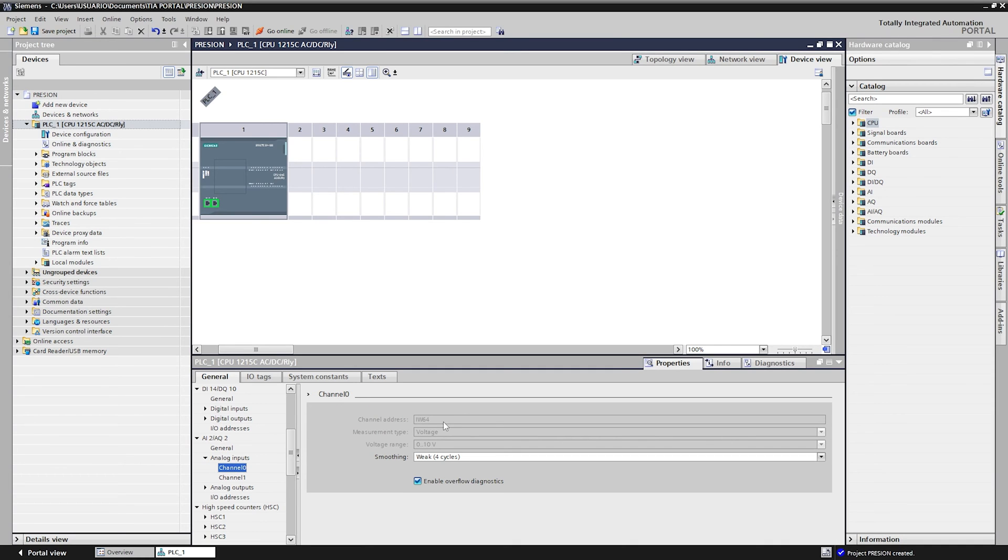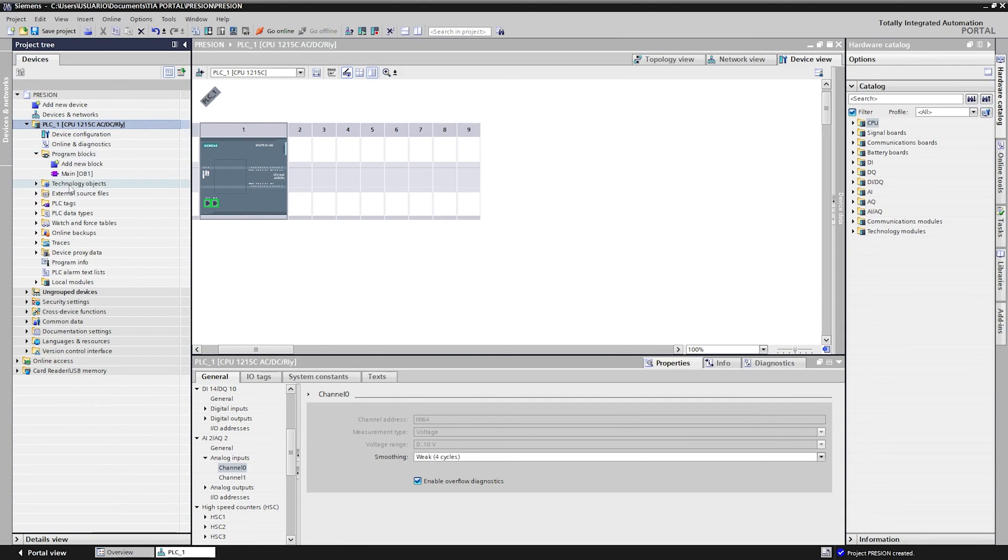It is connected to channel 0. The address we will use will be IW64, which receives the signal 0 to 10 volts. Now in programming we need to scale the signal in units of pressure in this case pound per square inch, or known as PSI. We use the norm and scale block.